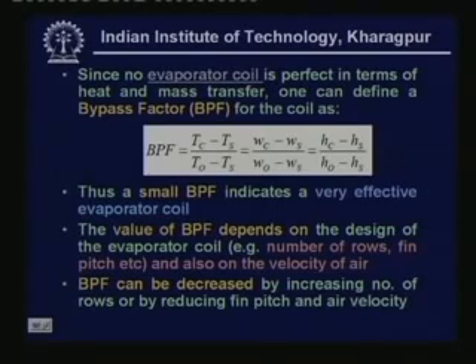The value of the bypass factor depends on the design of the evaporator coil, for example number of rows, fin pitch, etc., and also on the velocity of air. The bypass factor can be decreased by increasing the number of rows or by reducing fin pitch and air velocity. So the design of the coil decides the bypass factor. In addition to that, the air velocity also decides the bypass factor. For a given coil, if you reduce the air velocity, air has more time to spend with the coil, that means more dehumidification takes place and the temperature of the air goes nearer the coil ADP.